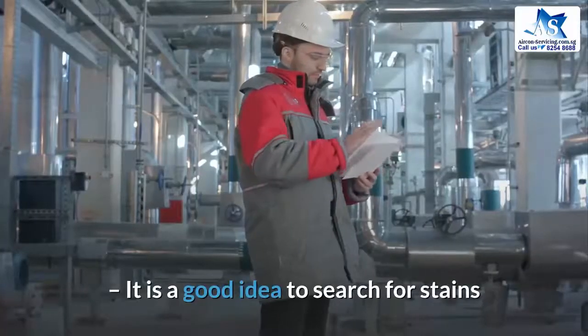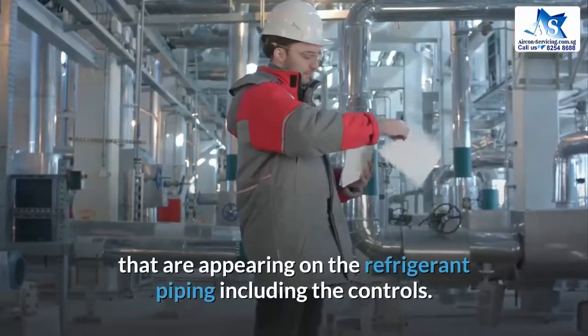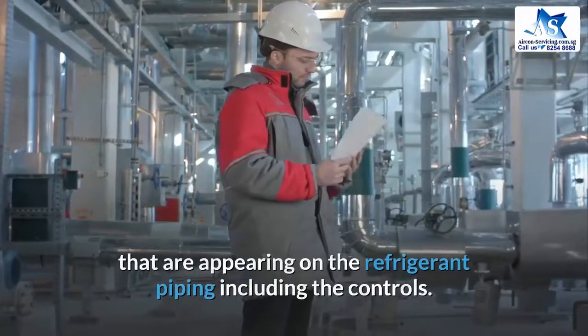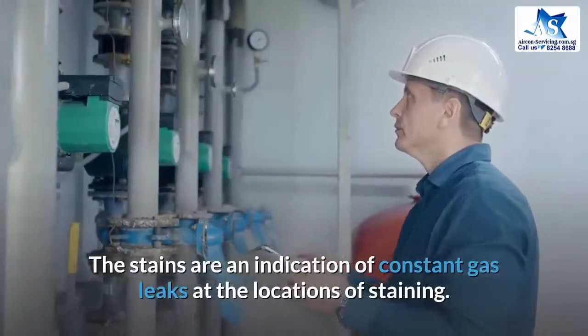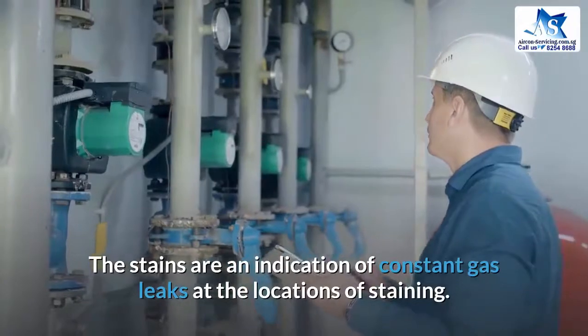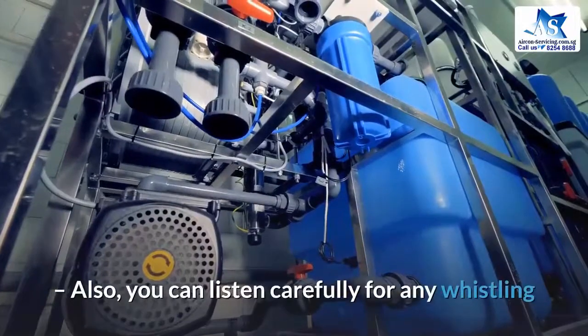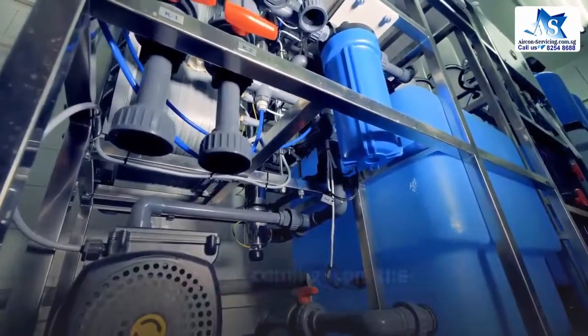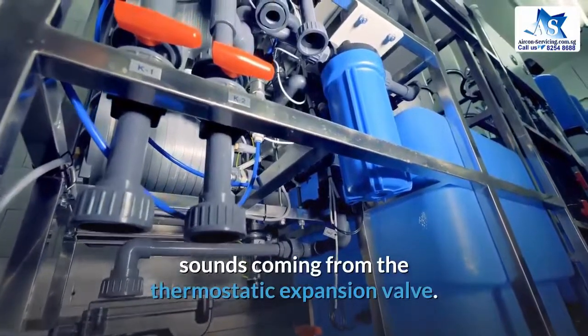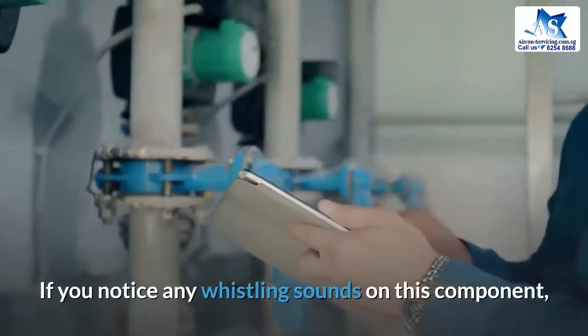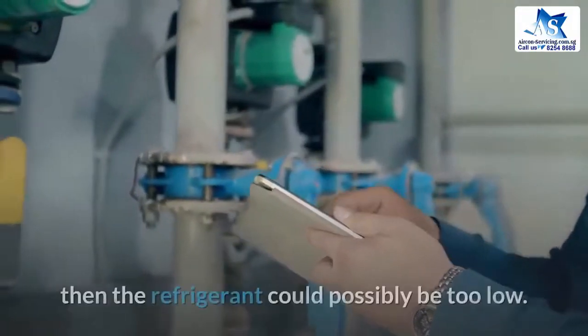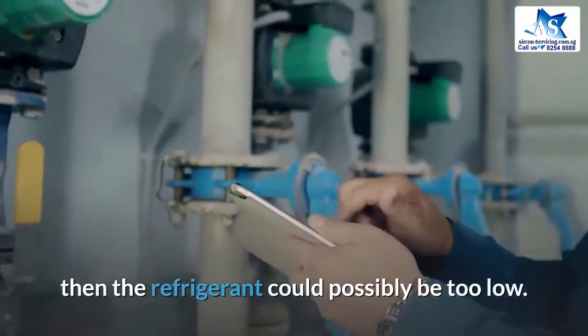It is a good idea to search for stains that are appearing on the refrigerant piping, including the controls. The stains are an indication of constant gas leaks at the locations of staining. Also, you can listen carefully for any whistling sounds coming from the thermostatic expansion valve. If you notice any whistling sounds on this component, then the refrigerant could possibly be too low.